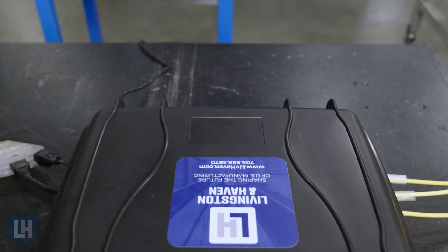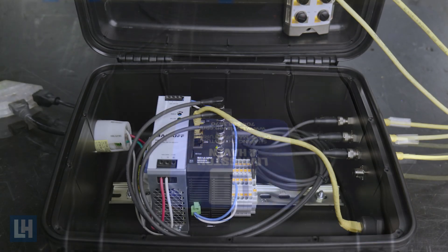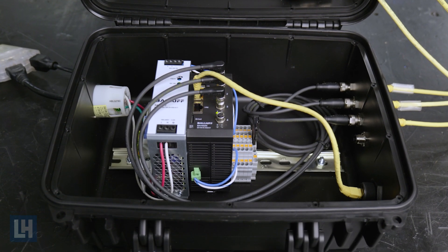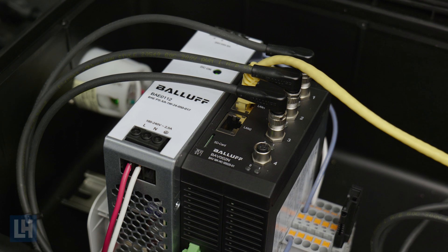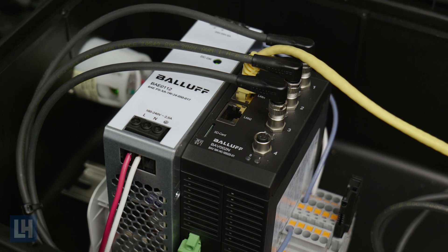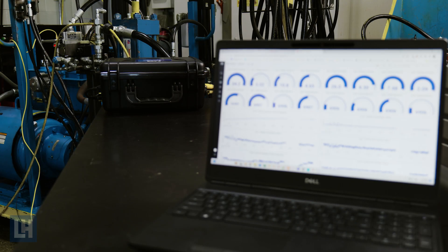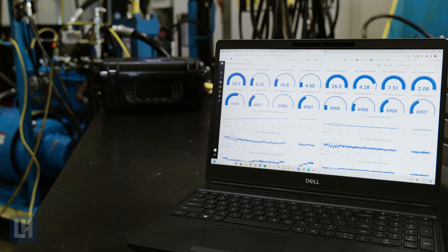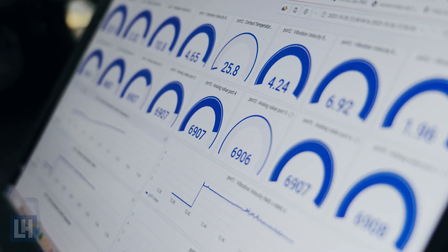The CMTK system operates independently of the machine controls and PLC, so it doesn't affect the performance of the machine. IO-Link based sensors connect to the CMTK base unit, which records data internally and communicates via an Ethernet or wireless connection to your network. The software on the CMTK allows you to visualize and analyze the data coming from your IO-Link based sensors and set acceptable ranges for normal operation.